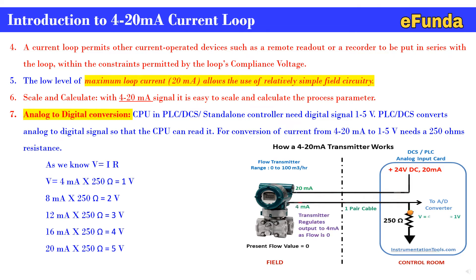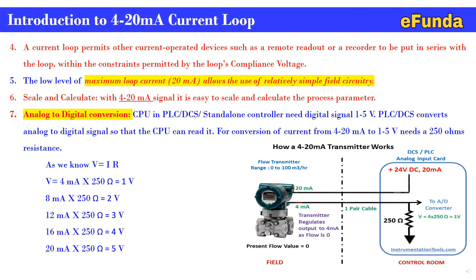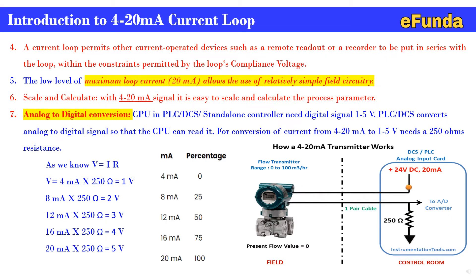Continuing the calculations: 8 milliamp into 250 ohm gives 2 volts, 12 milliamp into 250 ohm gives 3 volts, 16 milliamp into 250 ohm gives 4 volts, and 20 milliamp into 250 ohm gives 5 volts.